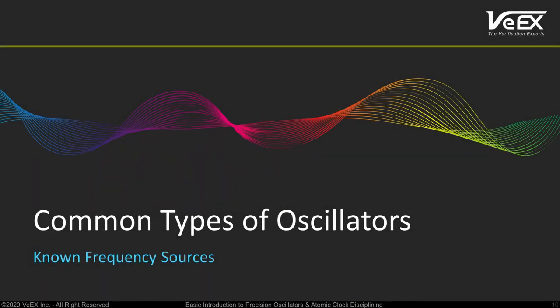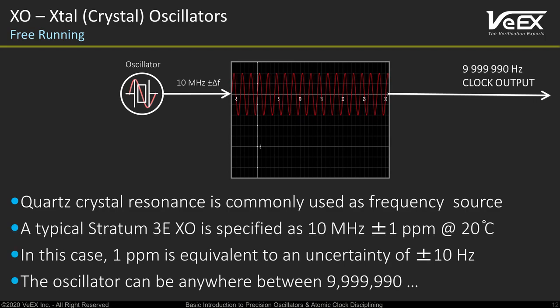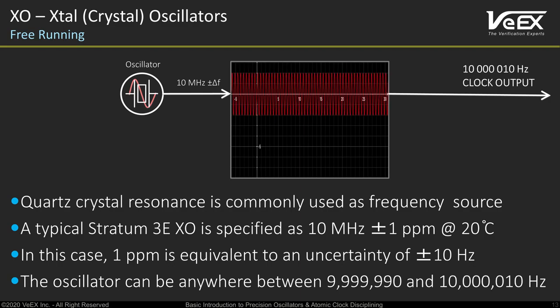Let's take a quick look at some common types of oscillators and get familiar with terminology and acronyms. Starting with the most common type, the quartz crystal oscillator — on its own it doesn't qualify as a precision frequency source, but it is an important building block for modern clocks. A modern stratum 3E quartz oscillator may have a typical specification of 10 MHz ±1 ppm at 20°C, that is somewhere between 9,999,990 Hz and 10,000,010 Hz — a lot of uncertainty. From the time point of view, 1 ppm is equivalent to gaining or losing 1 microsecond every second, which is not good. These days we prefer to see inaccuracies in the order of parts per trillion.